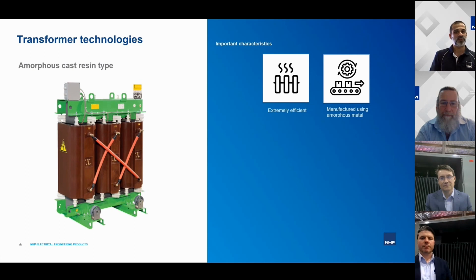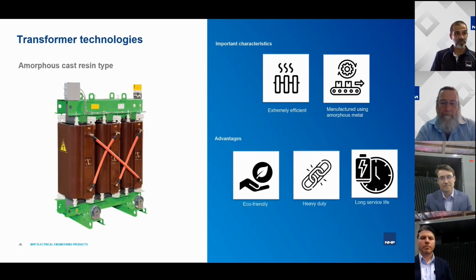Here, by using an amorphous core, which has an atomic structure different to standard laminated sheet steel, you get lower hysteresis losses, which in turn reduces your no-load losses by about 70%. So it's a significant reduction over the lifetime of the transformer, say if it was 30 years. I would like to pass on to Sean, who had a couple of good examples that he wanted to share with us around this type of technology. So over to you, Sean.